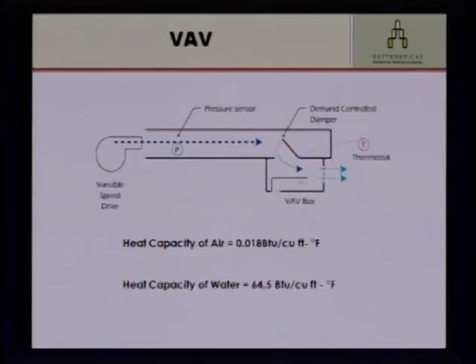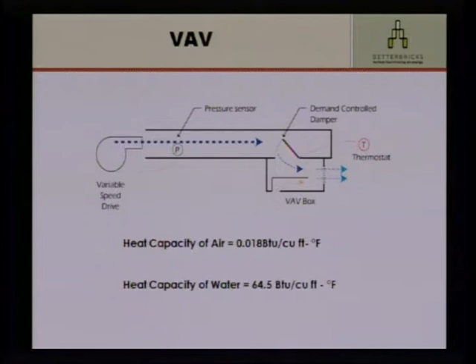Here we have the same problem, except VAV got rid of a lot of that constant mixing. It went to one duct, typically with a reheat option at the far end, so if it was too cold you could warm it back up a little. The problem isn't the mechanism, the problem is that you're using air to move energy, and air has two lousy properties.